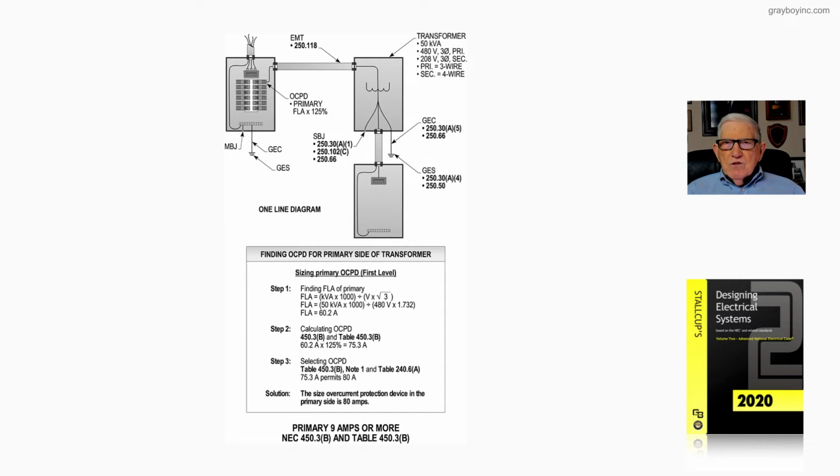However, if you had nuisance tripping, for a control circuit, you could refer to 430.72(C)(4), and you could use 500% if it became necessary where a control transformer was involved and you wanted to prevent nuisance tripping. Now basically those are the requirements of Table 450.3(B).